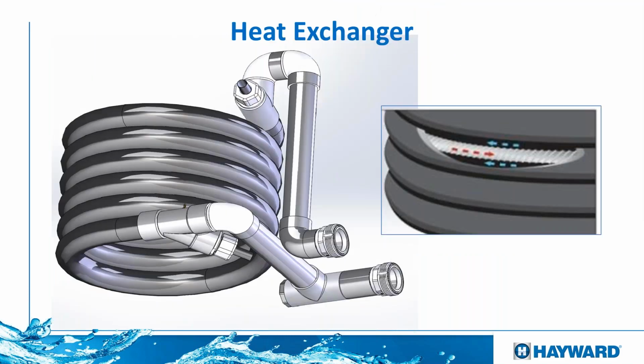And here we see more in-depth info on our heat exchanger. Remember that all of this tubing that you see inside here is titanium tubing. So that is what is in contact with the swimming pool water. It helps avoid any type of corrosion, because titanium is a very strong metal, especially compared to copper.